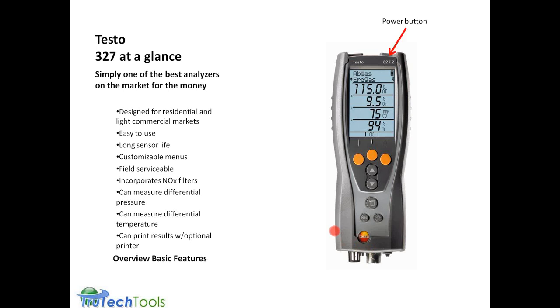So let's take a walk around the outside of the analyzer. Going from the top, there's, of course, the power button. It has a 1-0 on it. It's a little one nestled in the top ledge of the product. The drain plug, which is used to, if you recall back, we talked about water vapor being present as a combustion byproduct. Well, water will eventually, the vapor will condense and form liquid water.